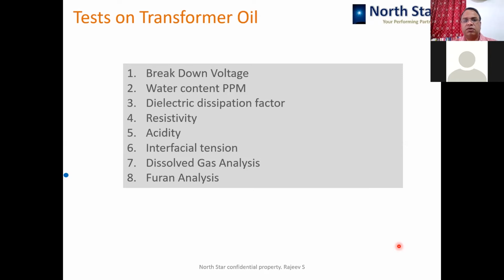We should also talk about tests like IFT and acidity and tan delta. Breakdown, water content, and resistivity can be done as more frequent tests. But just doing BDV is not advisable, especially when the transformer is of higher rating.